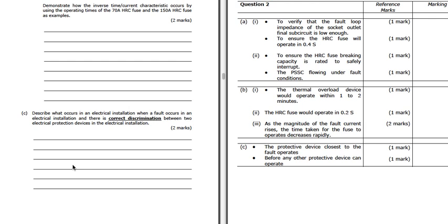Describe what occurs in an electrical installation when a fault occurs and there is correct discrimination between the two devices. So when we've got correct discrimination, the protective device closest to the fault operates before any other protective device can operate.